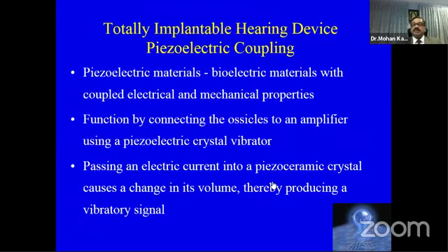So the sound hits the drum, the ossicular chain vibrates, and this vibration is picked up by a piezoelectric crystal. This is known as a sensor, and it is placed on the part of the ossicular chain which vibrates most, or the maximum oscillation. And this is the body of the incus, very close to the head of the malleus, so very close to the joint. So the body of the incus is a place where the ossicular chain vibrates most.